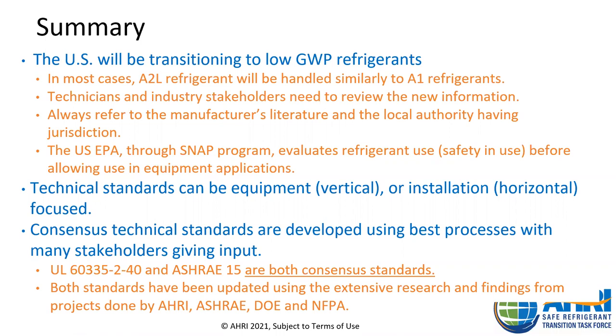Always remember the two golden rules. Always refer to the manufacturer's literature and the local authority having jurisdiction when it comes to any questions regarding an installation of a system with an A2L. The US EPA, through the SNAP program, evaluates refrigerant use for safety and use before allowing use in applications. The technical standards can be equipment, which are vertical, or installation, which are horizontal focused. Consensus technical standards are developed using the best processes with many stakeholders giving input. Many of you here today were involved in the writing and shaping of the standards that are currently in place.